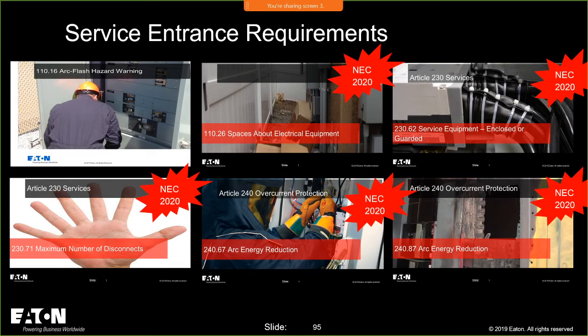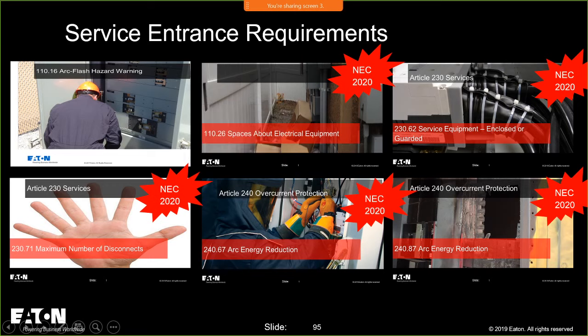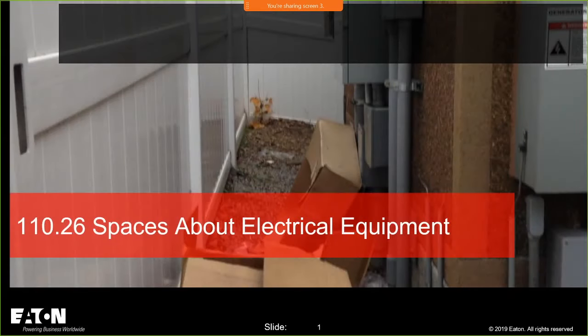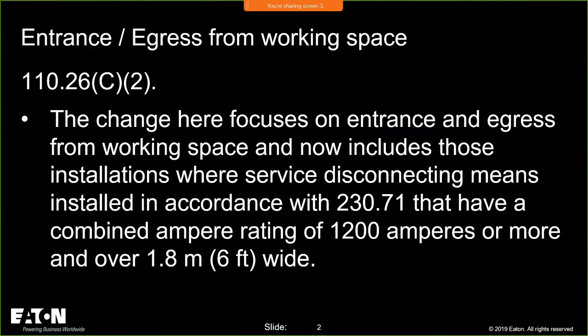So I'm not going to hit 110.16 right now. I'm going to move into 110.26 working space, because it's not necessarily associated with service entrance requirements, but I liken it there because the service entrance equipment is probably going to be one of the largest pieces of equipment, and the change that was made in 110.26 was around large equipment. So if you think about 110.26(C), entrance to and egress from working space, what they focused on was the electrical worker. There's a rule in there that says if your overcurrent device is 1200 amps and above, then you have to have another entrance.